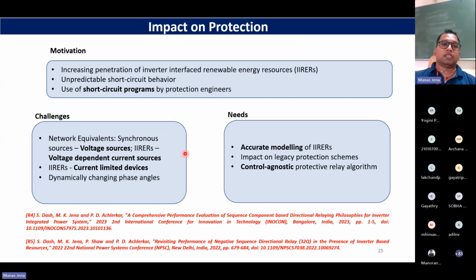This type of unpredictable behavior from inverters comes from current limiting devices, voltage dependent current sources, and dynamically changing phase angles because of the control action. And the protection is actually designed assuming that the source is a very nice voltage source. So what I am trying to convey is that all these legacy protection schemes need to be revisited, and their performance needs to be evaluated in the presence of inverters with different control philosophies.